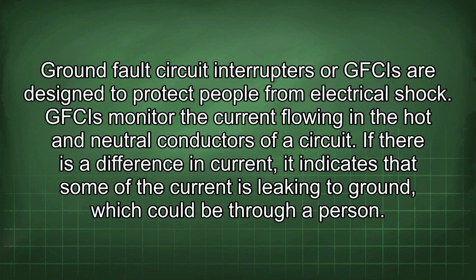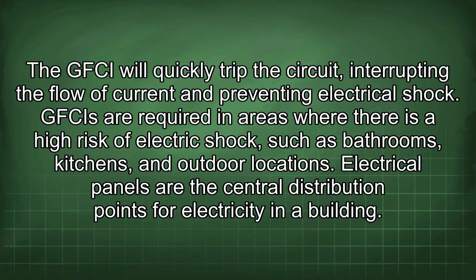Ground fault circuit interrupters, or GFCIs, are designed to protect people from electrical shock. GFCIs monitor the current flowing in the hot and neutral conductors of a circuit. If there is a difference in current, it indicates that some of the current is leaking to ground, which could be through a person. The GFCI will quickly trip the circuit, interrupting the flow of current and preventing electrical shock. GFCIs are required in areas where there is a high risk of electric shock, such as bathrooms, kitchens, and outdoor locations.